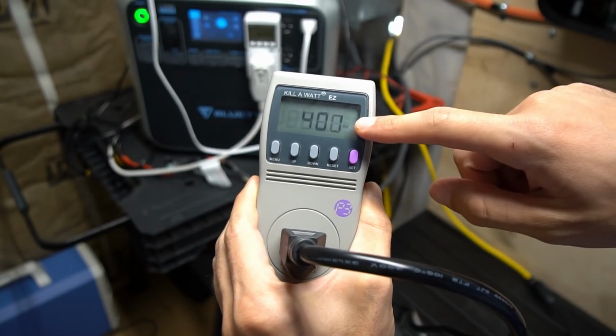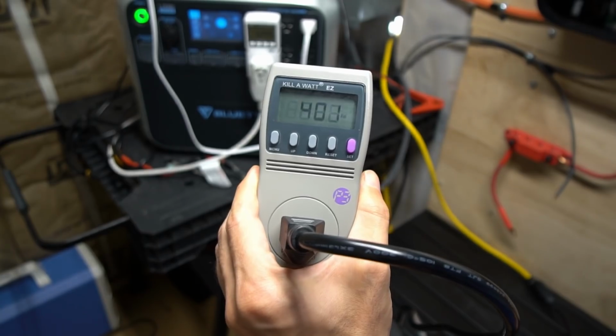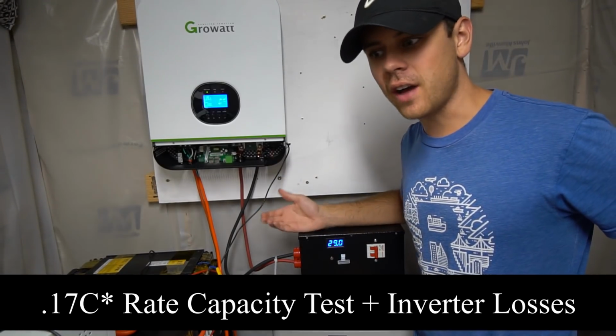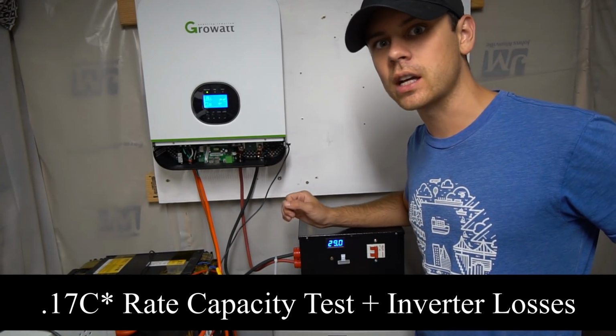We're going to pull a constant 400 watts until the battery is dead. That'll take about 5 hours, so this is a 0.2 C rate capacity test.